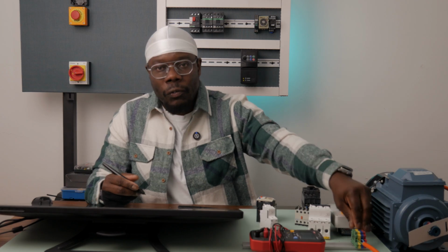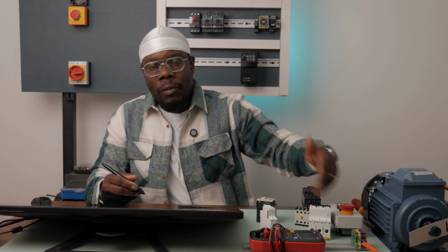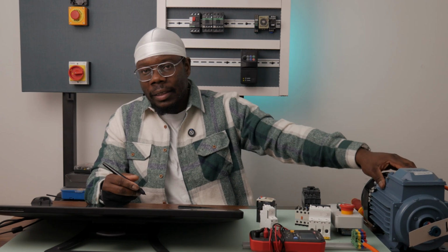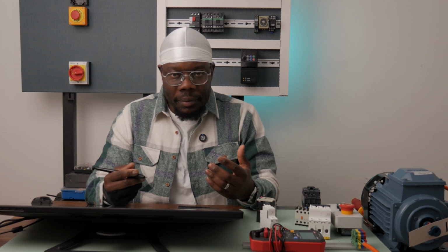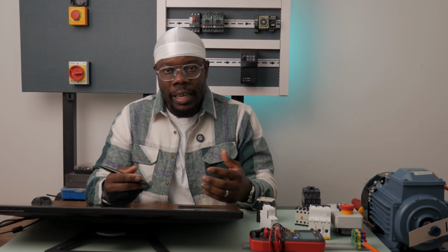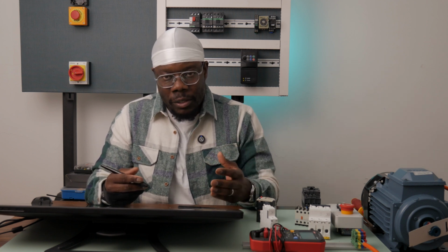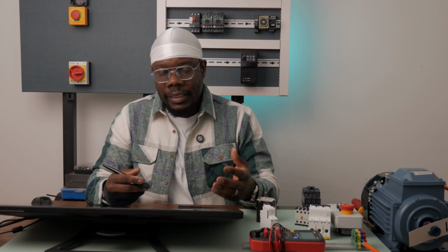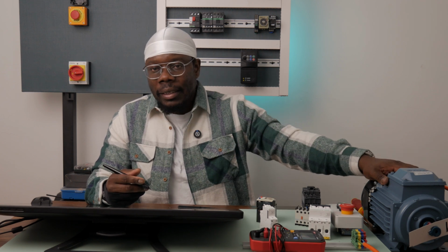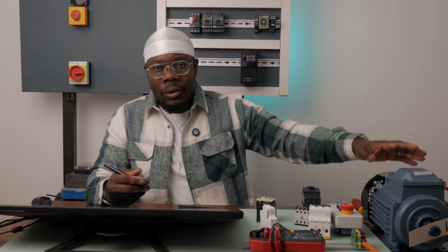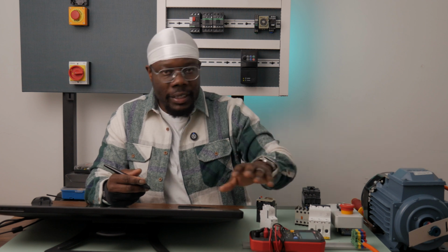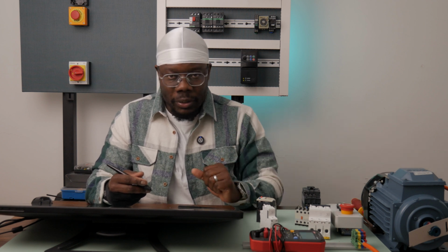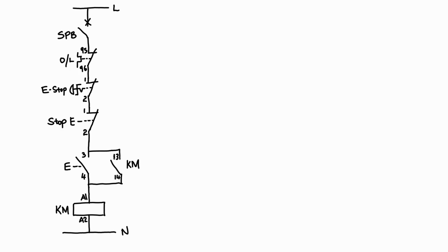I have the control voltage supplied separately from the three-phase supply that's going to run this motor, because where I am here, I don't have a three-phase supply. So I'm going to use a variable speed drive to generate the three-phase that I'm going to require to run this electric motor. So I cannot use one of the phases from that variable speed drive. Okay, so basically, this is the control circuit.